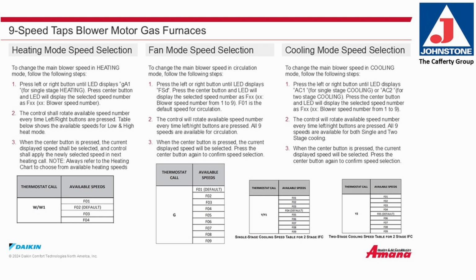9-speed taps blower motor in gas furnaces. Heating mode speed selection. To change the main blower speed in heating mode, follow these steps. Press the left or right button until the LED displays GA1 for single-stage heating. Press the center button and the LED will display the selected speed number as F and 2 digits, 01 through 04. The control will rotate available speed number every time the left or right buttons are pressed.